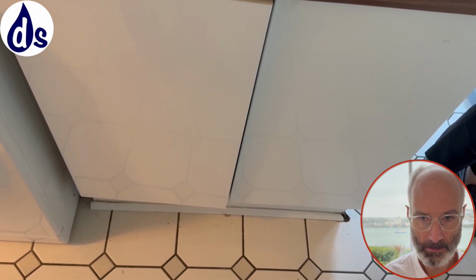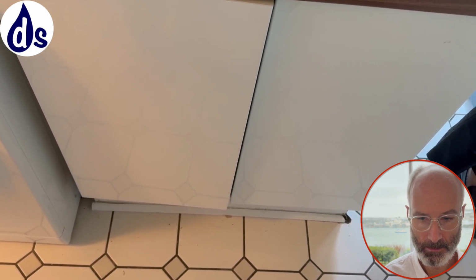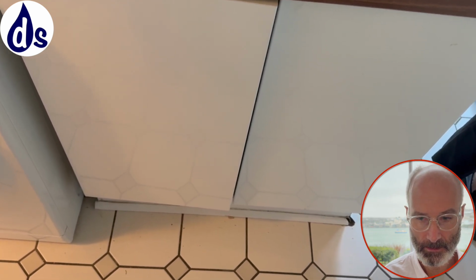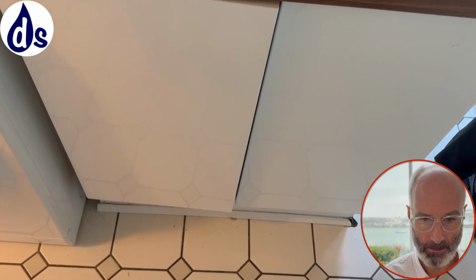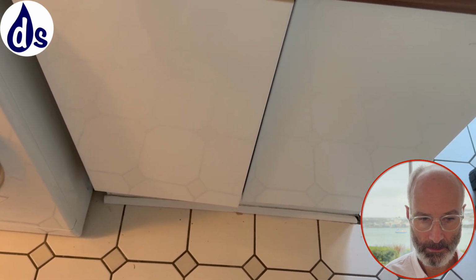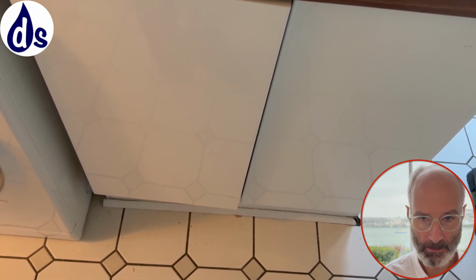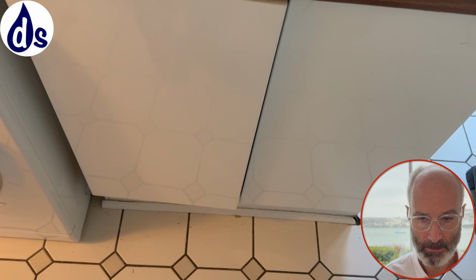So you have to focus on targeting the source of the vapor, which are bathroom, kitchen, cooking, and drying clothes internally. I happen to see the clothes are being dried internally without a dehumidifier, so you need to have that. And then obviously respiration, which is not much you can do about, but that's why you need some background ventilation and/or dehumidifiers. I think every property should have a dehumidifier, in my opinion. It's the best way of dealing with excess vapor. It's much more energy efficient. It's much greener than over ventilating a property.